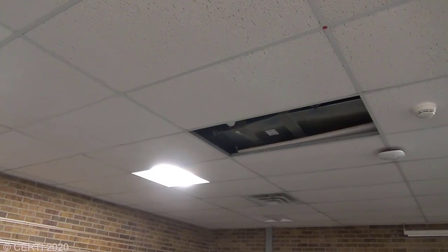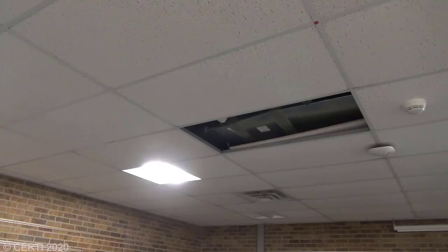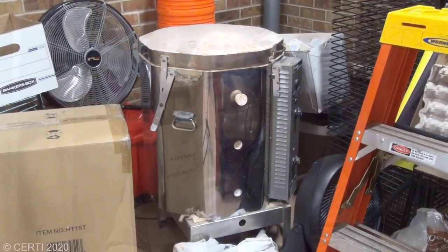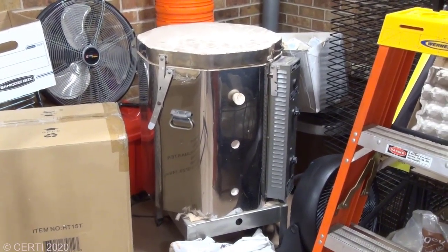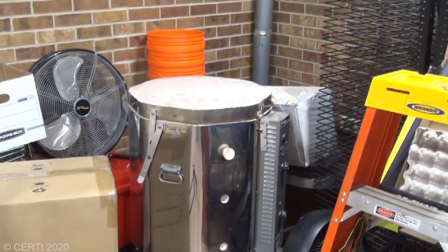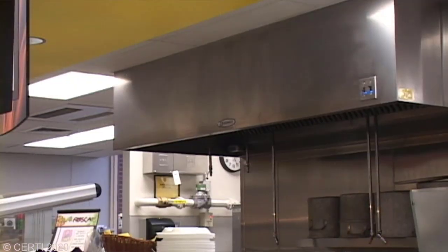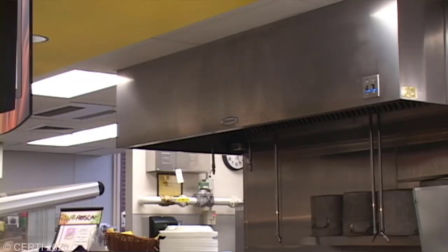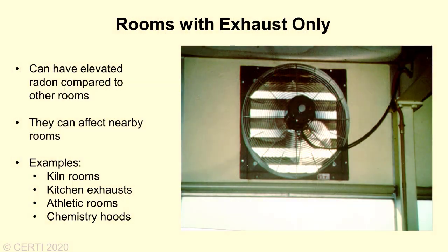Of course, missing ceiling tiles in such a system can also create negative pressures in a given room. There may also be rooms that are exhaust only. An example of this might be a room with a kiln for a pottery class, where hot air is exhausted to the outdoors, or perhaps kitchen hoods in the food preparation area. In these cases, there should be a means for providing additional outdoor air to replace the exhausted air when the exhaust fans are switched on. If not, this individual room, as well as other rooms communicating with it, can have high radon levels.